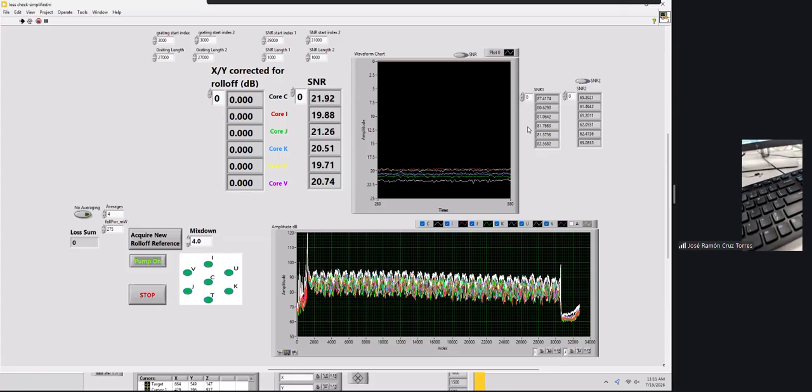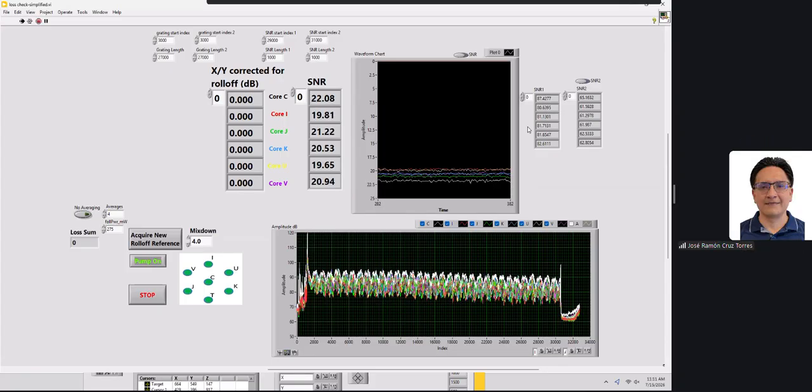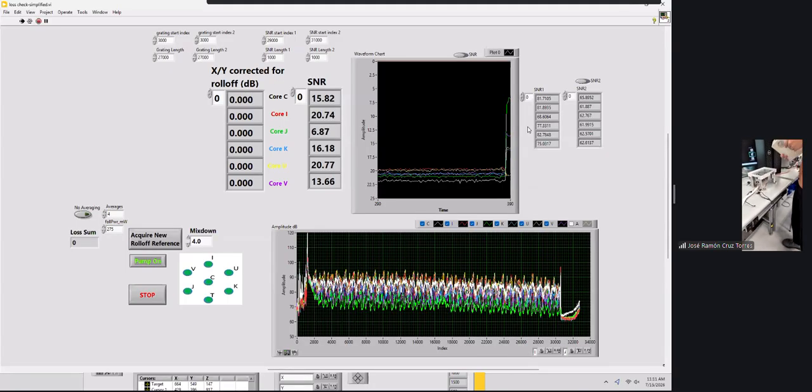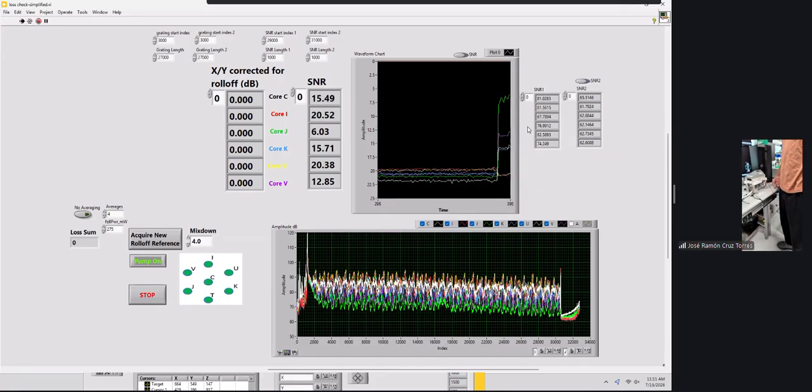So this is the block carriage that we did for this testing. We'll probably have something very similar, or just on an actual fin. But what we did for the longest time, while we're doing this repeatability testing, is just putting it on top, and that's it. Then you click start, and what it should do is just align. Take it off, do it again with a different catheter.